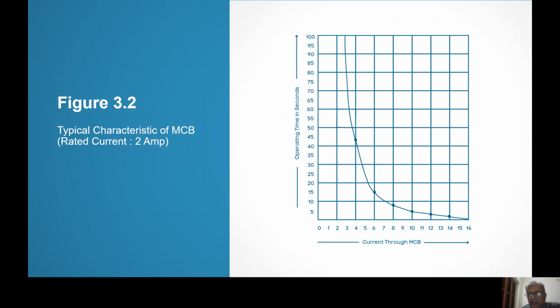I mean, a typical characteristic is like this. At 2 ampere it does not operate. Beyond 2 ampere, say at 4 ampere, at some point around 45 seconds, it operates. At 6 ampere, it operates within 15 seconds. Like that, you get the inverse curve and you come to know that the MCB works exactly as it is desired to work. My equipment is going to be damaged if the current is large, and it is going to be damaged faster. Therefore, my MCB also trips faster.